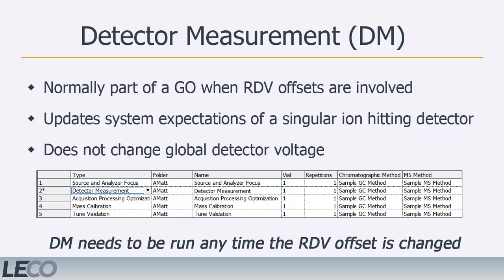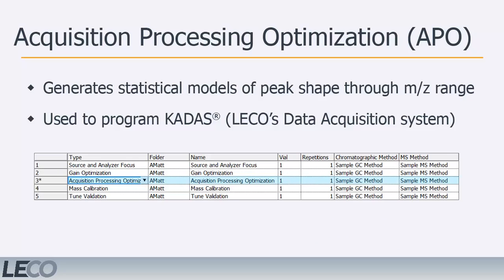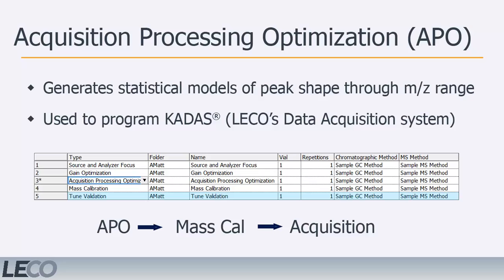The Acquisition Processing Optimization, or APO, collects profile data of PFTBA and generates statistical models of peak shapes through the mass-to-charge collection range. This information allows the KADAS to efficiently convert and condense sample data in real time. Once the APO has finished, a mass calibration must be run before continuing to sample acquisition.